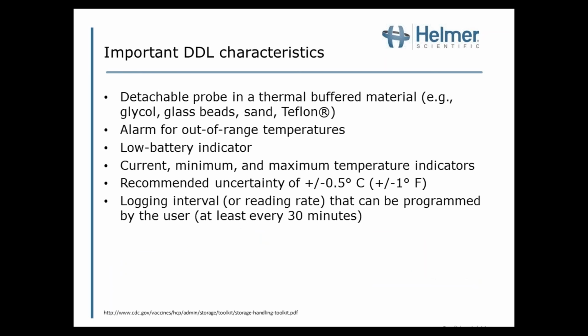So as I mentioned, some important characteristics is that the probe is in a thermal buffered material. Oftentimes that's glycol. It can be some other materials as well. An alarm for out of range temperatures is really nice, and some of the newer thermometers will even hook up to the cloud where you can access it with an app on your smartphone, and it'll let you know even if you're not in the site if you've had an excursion. A low battery indicator is important.